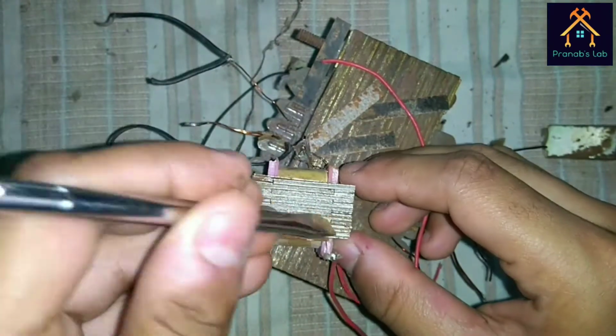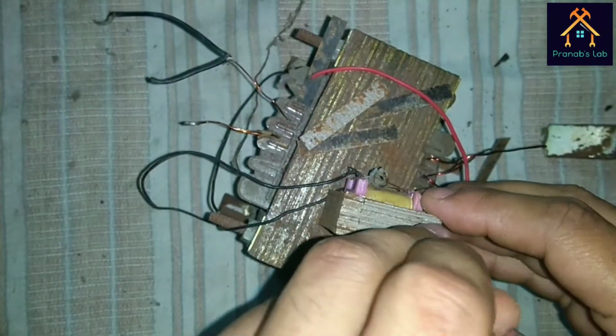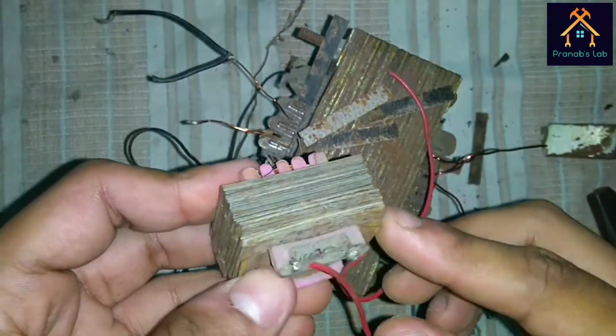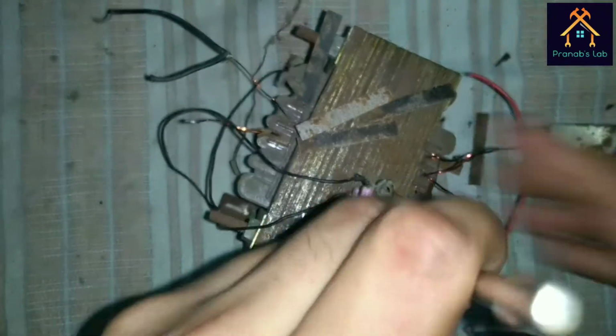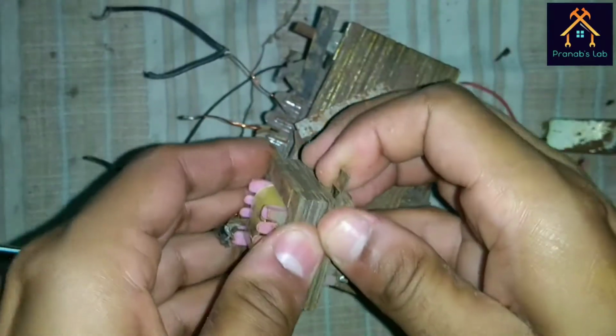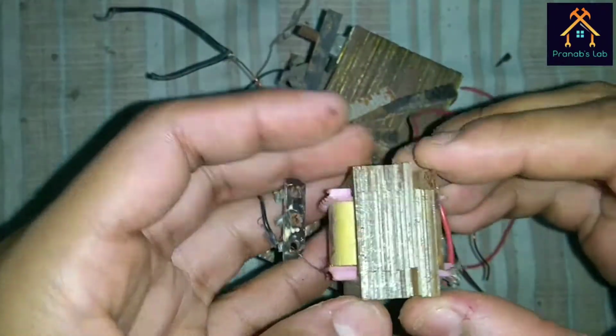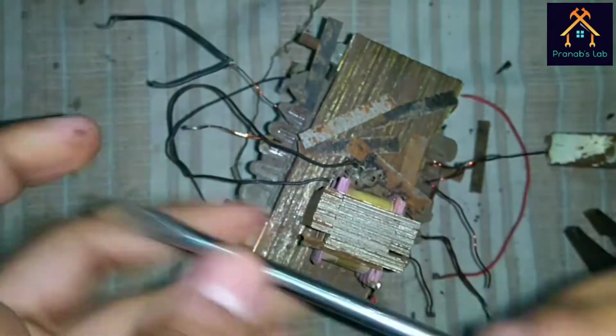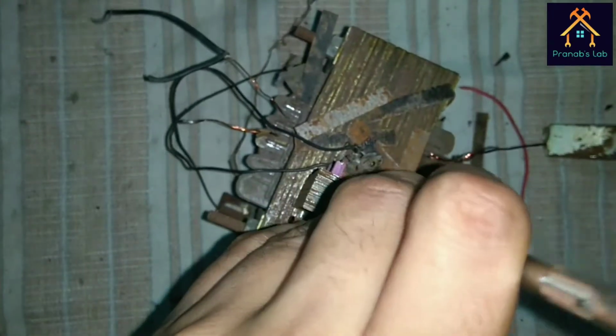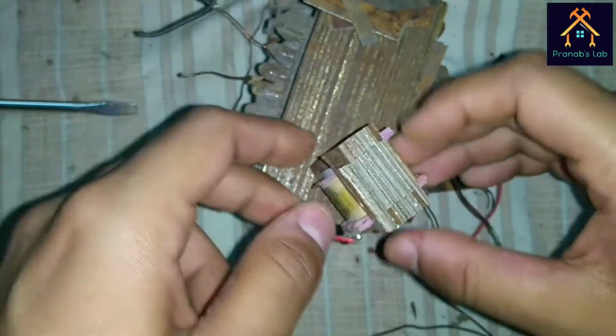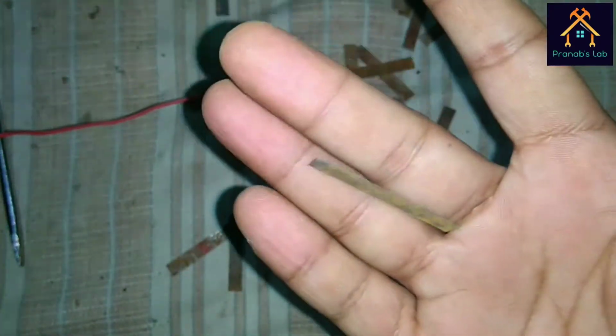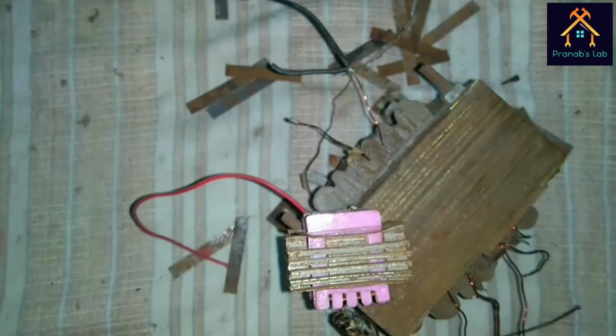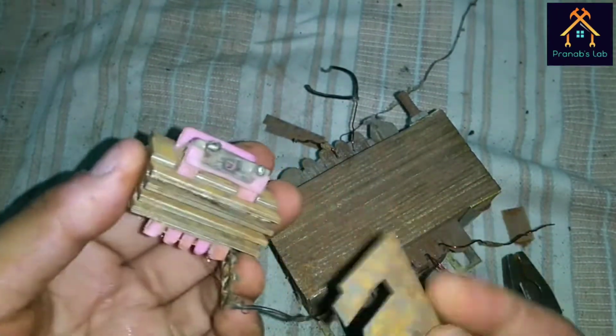This core helps to carry the magnetic flux and hold the windings. You can see the I sections are coming out. By pressing it, you can remove the I sections by using a plier. Now you can see all the I sections are removed and the core looks like this, and these are the I sections removed from the core. Now we have to remove the E sections from the transformer core. Now you can see the E sections are coming out from the former.